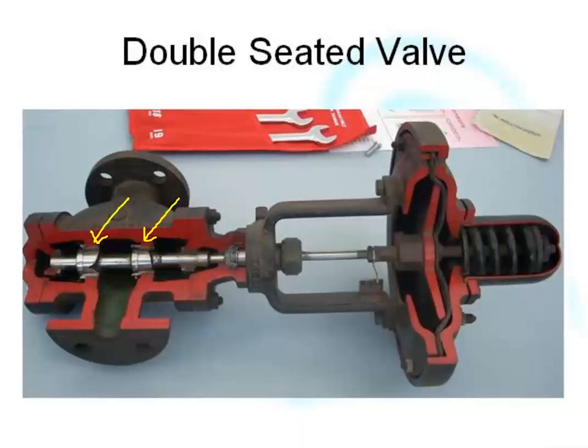While we're looking at this valve, I'd just like to point out some other things. At the top here we have a spring. This is a spring return valve, and it's a strong spring. This is a very, very strong spring. Valve actuators generally have very strong springs on them, so you're always a little bit careful when dealing with a valve actuator, because if you just unscrew it willy-nilly and that spring comes out, it comes out with some degree of force. Just here, of course, that's the diaphragm, and we blow air into the top and it pushes the stem downwards in this case.